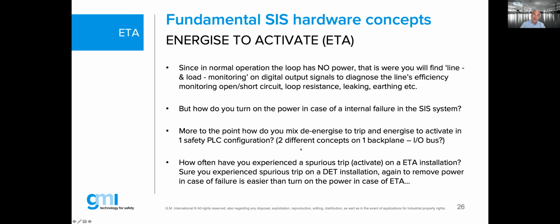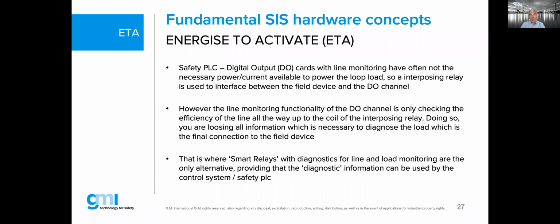Now, if you think about that, I'm pretty sure that the de-energized to trip examples, you have plenty of experience that you have seen a spurious trip in the field, that actually your functionality goes to a shutdown without any reason. We call this nuisance trip, spurious trip. Those are the ones that your process production people, your managers, your supervisors are hating because they lose production. Opposite, if you have energized to activate, I'm pretty sure it's very rare, if any, that you have seen ever in your lifetime a spurious trip, that your energized to activate was activated without any reason. That means there must be something in our configuration different, that we experience spurious trip in de-energize a lot, but in energized to activate, we don't experience the same. And that's something that we want to highlight here.